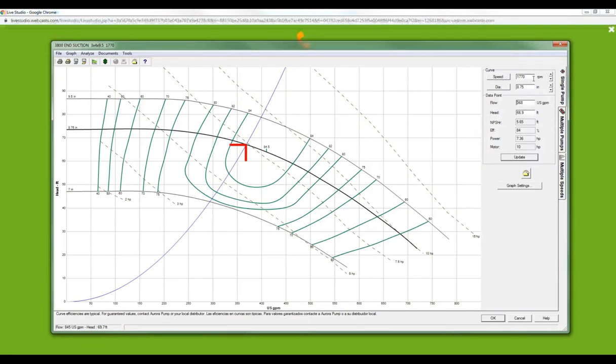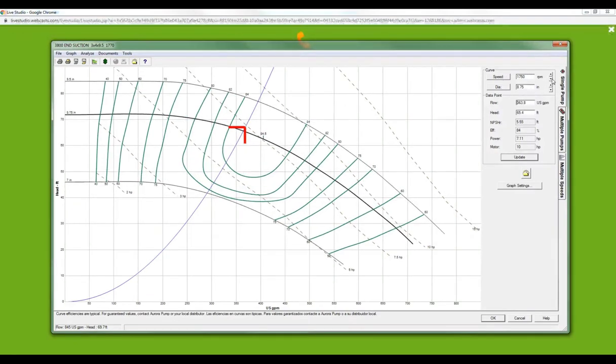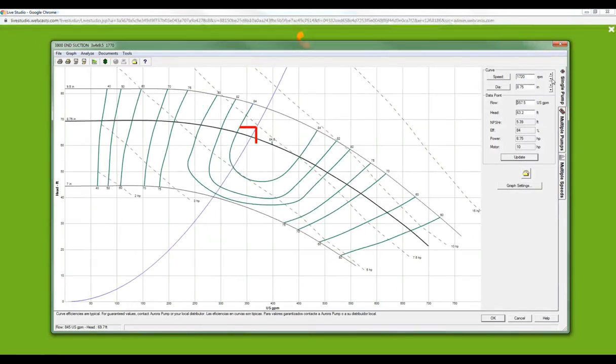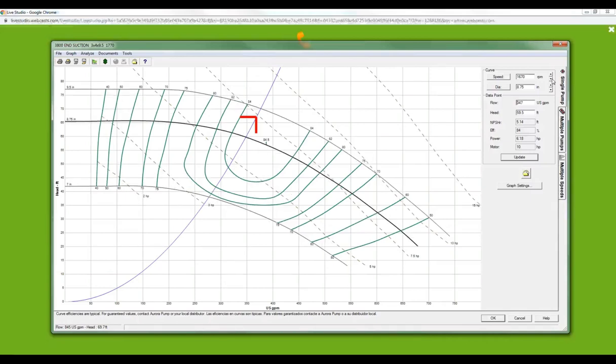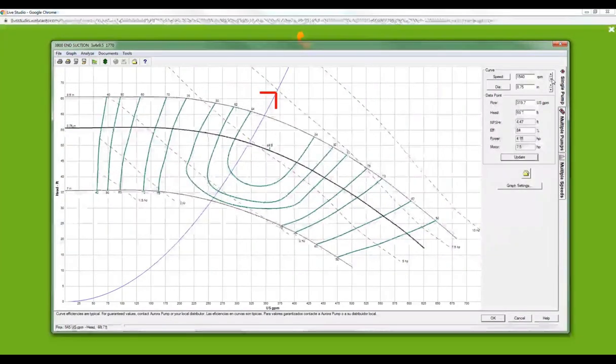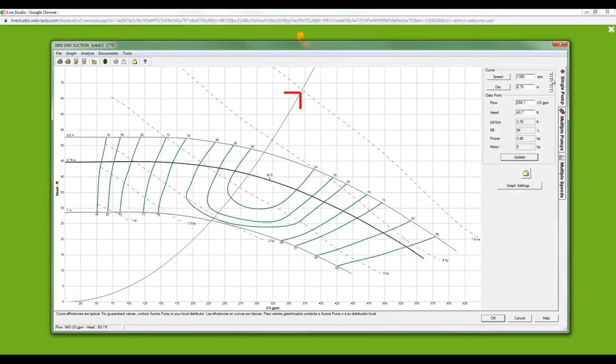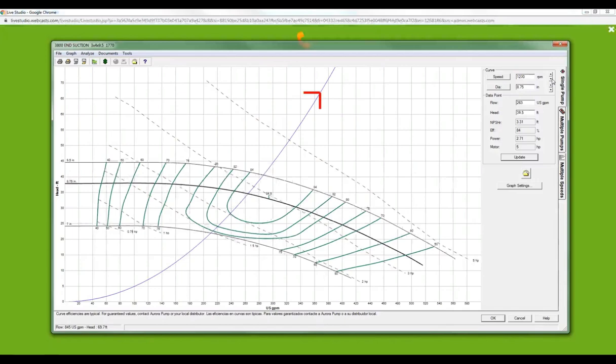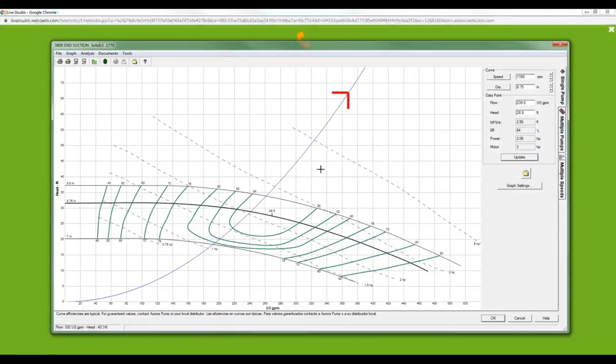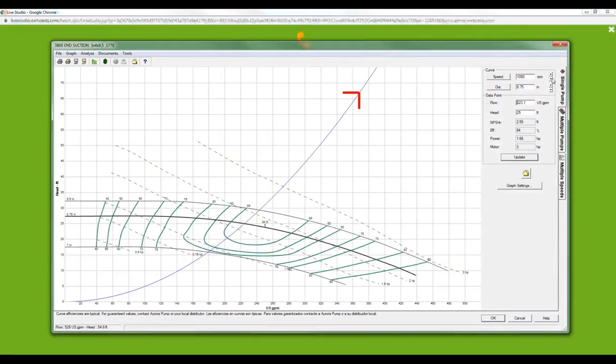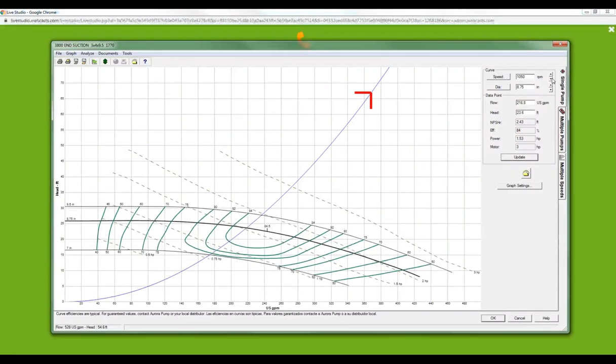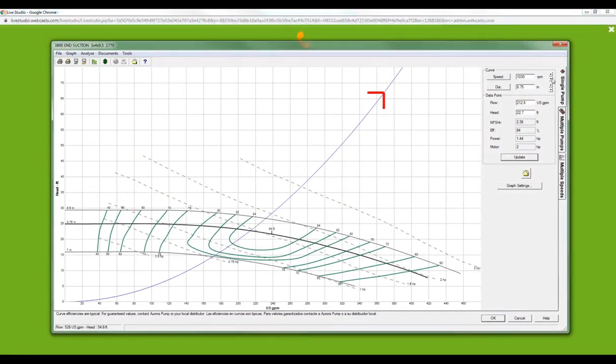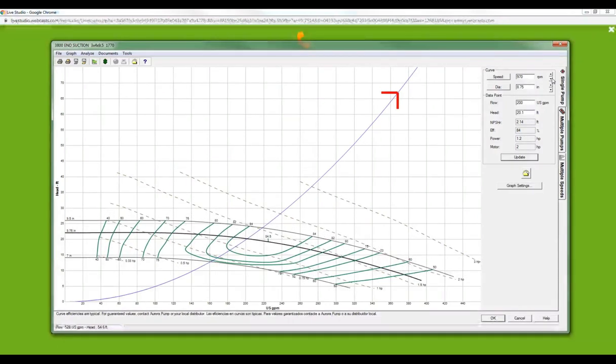If we come up here to the RPM, and I bring that down, there's 1760. Notice that the pump curve is moving down the system curve. And we want to get it down to 200 gallons per minute. Coming down, coming down, coming down. We're getting sort of close. Here we are at about, that intersection now is about 240. I need to get it down here to 200. Coming close. So let's bring that right down there, just about got it. There we are. 200 gallons per minute.